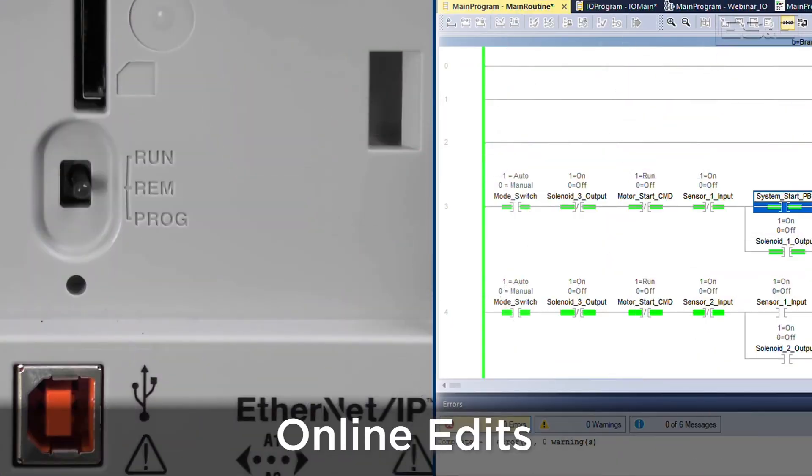When in remote, you have to ensure that you do not put the controller in remote program when the machine is running because it will stop executing the code. When in remote, you can make online edits, which is a feature that can be very powerful. It allows you to make changes to the logic without stopping the process.